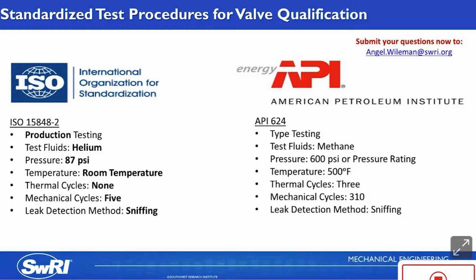Testing with methane lowers the maximum test pressure to 600 psi, or the pressure rating of the valve if it's lower than that. It also lowers the temperature to 500 degrees Fahrenheit, and this puts some distance between the test temperature and the auto ignition temperature of methane, which is around 1100 degrees Fahrenheit. The standard requires 3 thermal cycles and 310 mechanical cycles, and the only approved leak detection method is sniffing since the leakage is a concentration, not a leak rate.